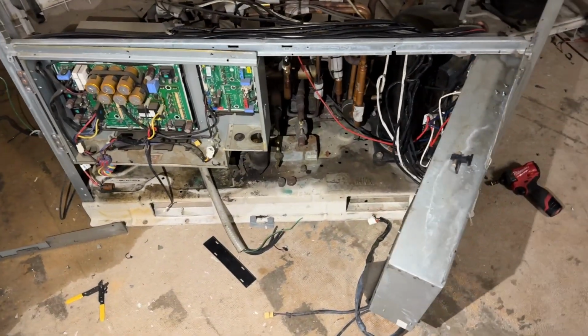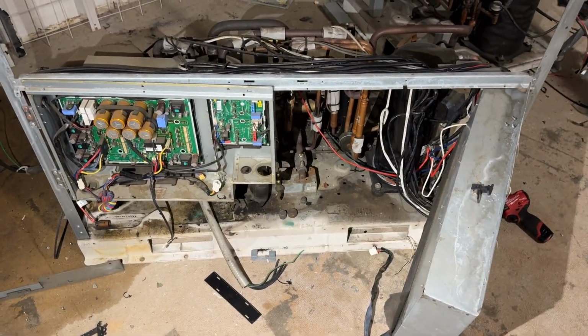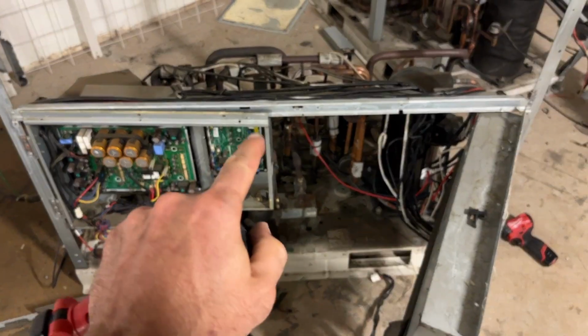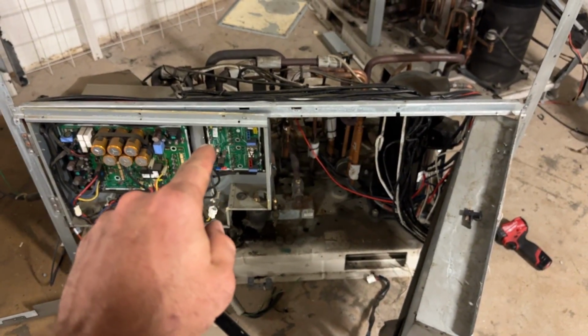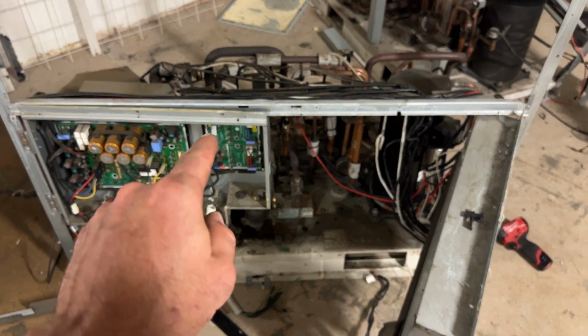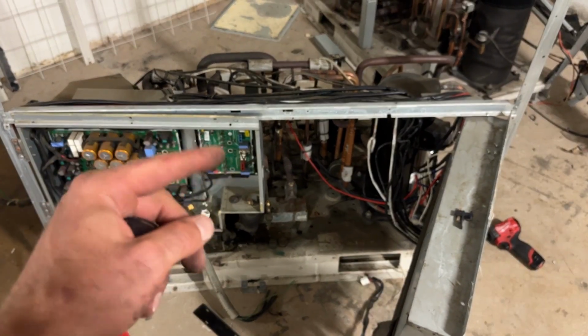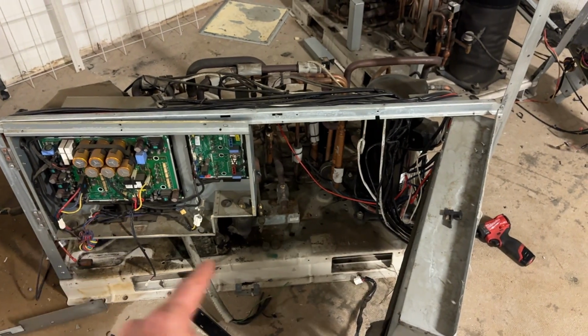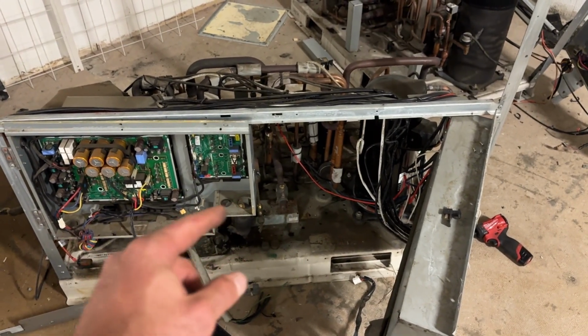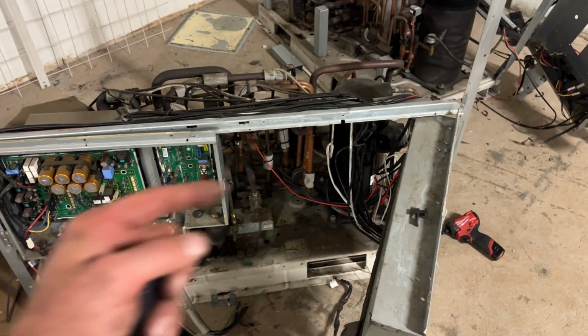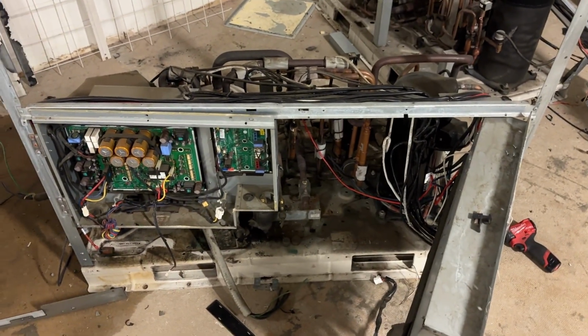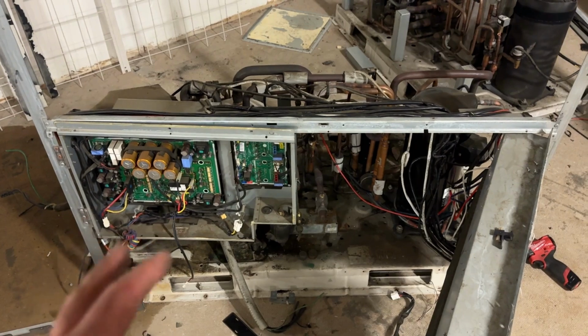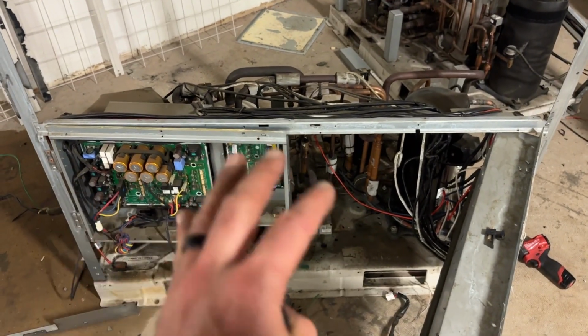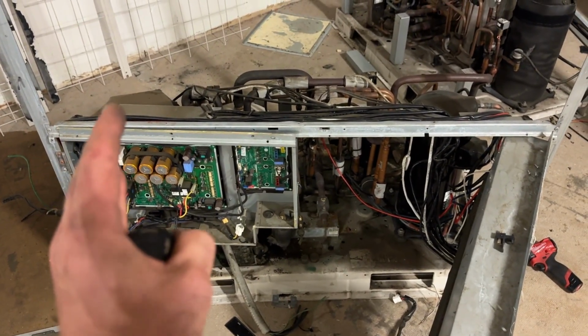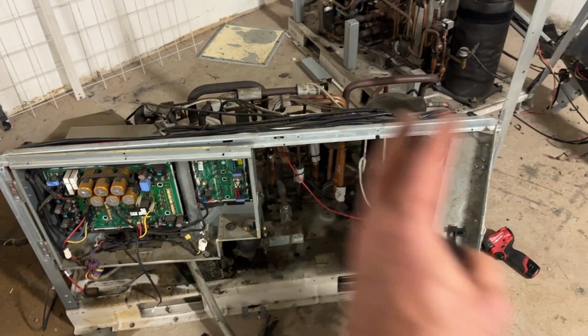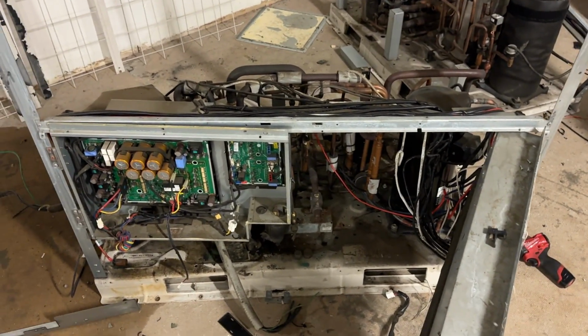And if you don't know, the beauty of the branch box is that when you have an indoor unit that's in heat, it's taking in that hot gas and condensing it in the coil. Well, instead of that liquid being sent back, it can just be sent to another unit that's calling for AC. So they can literally, very easily, without a lot involved, send heat from one side of a building over to the other side.